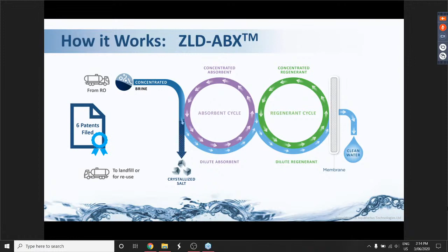The water is then passed to the regenerant cycle. The regenerant is used to dry the absorbent, so the absorbent is able to reconcentrate back up so it can absorb more water. Now, the water moving into the regenerant means that we need to take the water out of the regenerant so that it can be reconcentrated back up for use again. We pass it across the membrane, and you get clean water on one side and dry regenerant on the other side. And that is how we are a non-thermal technology. We have 6 patents filed, and this is over our absorbent, regenerant, and the process.